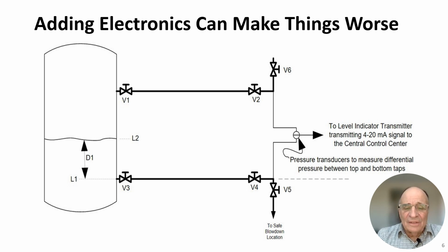So here's our typical level gauge, and what we had here before was a glass that somebody had to read, or a glass that we then put a magnetic disc in and a sensor on the outside of the glass, and that sent back information to the control room. Now we're going to put in a transducer that's going to look at the differential pressure between this point and this point, which should correspond to the differential pressure between here and here. But when you add a transducer and a transmitter, you now have a level transmitter, which typically operates at 4 to 20 milliamp signal, and it's very dependent upon who set it up.